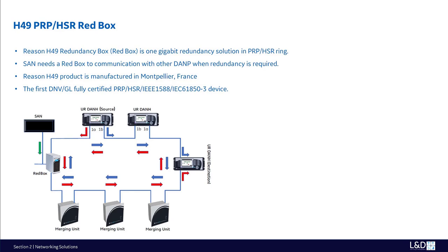A device with only one port, such as a printer or computer, is called a singly attached node, SAN. It is a node with a non-redundant network adapter. A SAN can communicate with other SANs and DANs, doubly attached nodes running PRP, on the same LAN. When a SAN is attached to a redundant LAN by a redundant Red Box device, the SAN can communicate with all the other DANs and other SANs in both LANs. In other words, if redundancy of a SAN is required, the SAN is connected to both LANs through a Red Box.